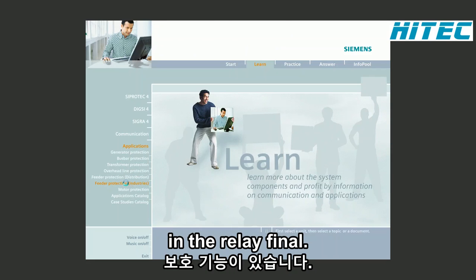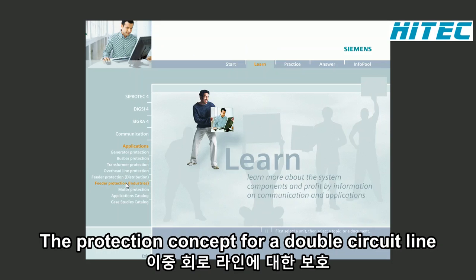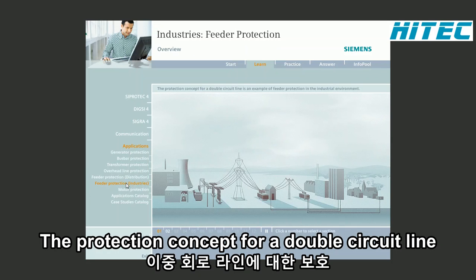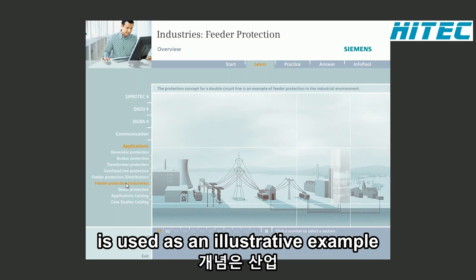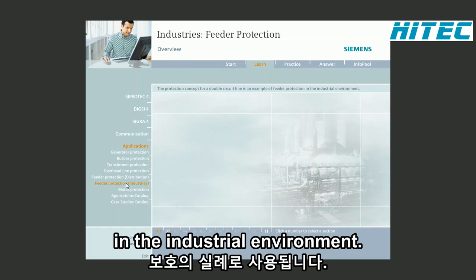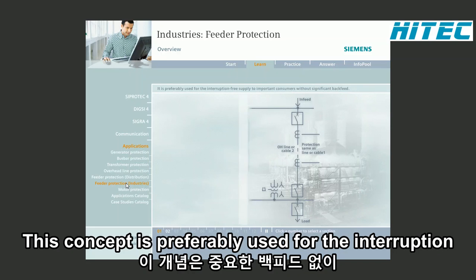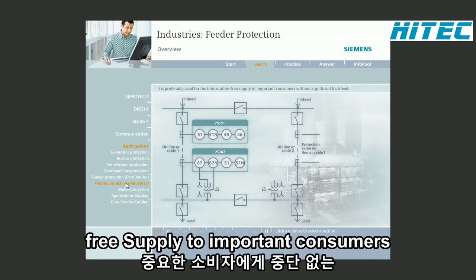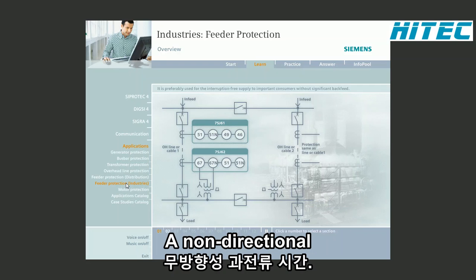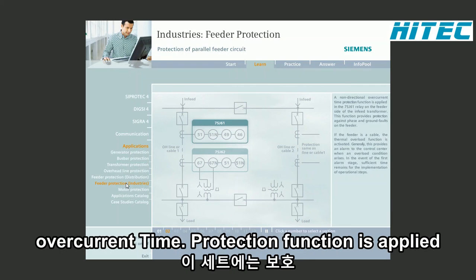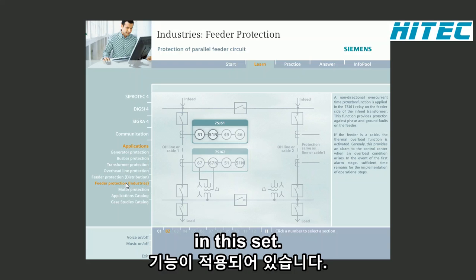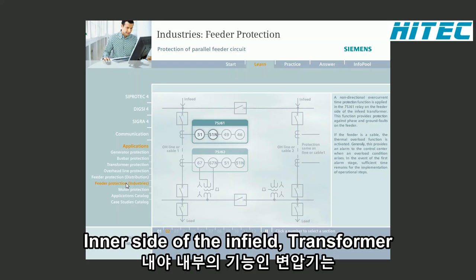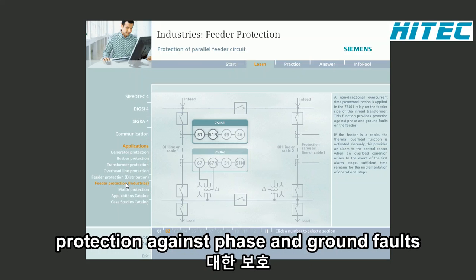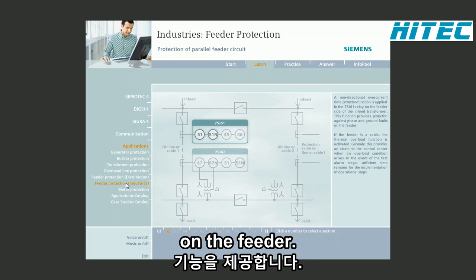The protection concept for a double circuit line is used as an illustrative example of feeder protection in the industrial environment. This concept is preferably used for the interruption-free supply to important consumers without significant backfeed. A non-directional overcurrent time protection function is applied in the 7SJ61 relay on the feeder side of the in-feed transformer. This function provides protection against phase and ground faults on the feeder.